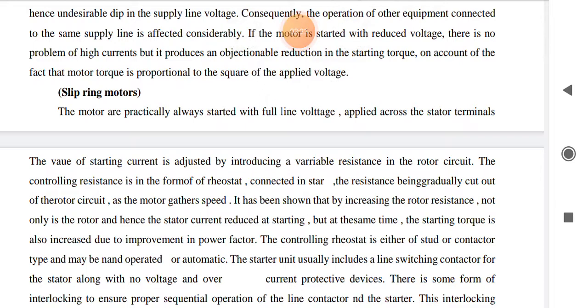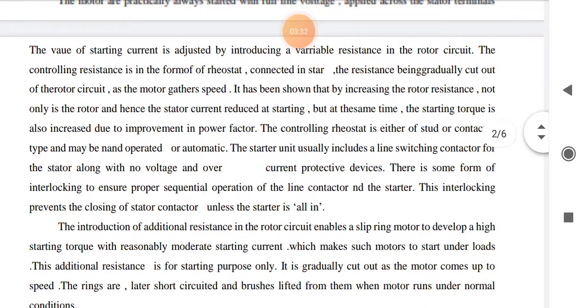Now we'll discuss the slip ring motors, the theory part. The motor is practically always started with full line voltage applied across the stator terminals. The value of starting current is adjusted by introducing a variable resistance in the rotor circuit. The controlling resistance is in the form of a rheostat connected in star, the resistance being gradually cut out of the rotor circuit as the rotor gathers speed. It has been shown that by increasing the rotor resistance, not only is the rotor and hence the stator current reduced at starting, but at the same time the starting torque is also increased due to improvement of power factor.